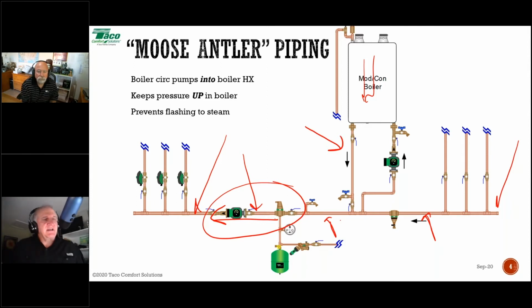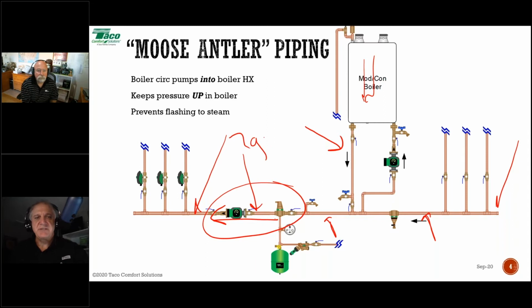Now, if my delivery is designed to a 20-degree delta T, we remember our universal hydronics formula, which states that GPM equals BTUH divided by the product of delta T times 500. So 70,000 BTUs divided by a delta T of 20 times 500, or 10,000, will tell us the flow rate through this header should be 7 gallons per minute, and we can size that pipe accordingly. 7 gallons a minute will typically be 1 inch copper. There's no harm in oversizing that header.